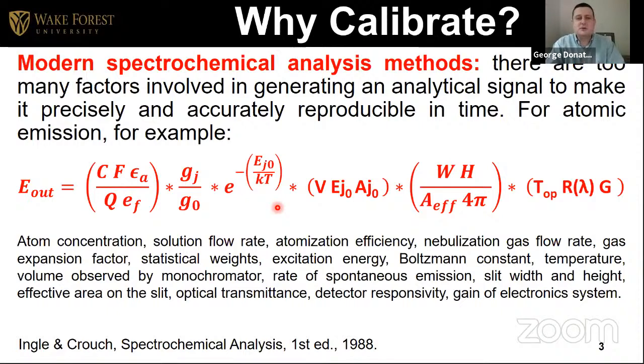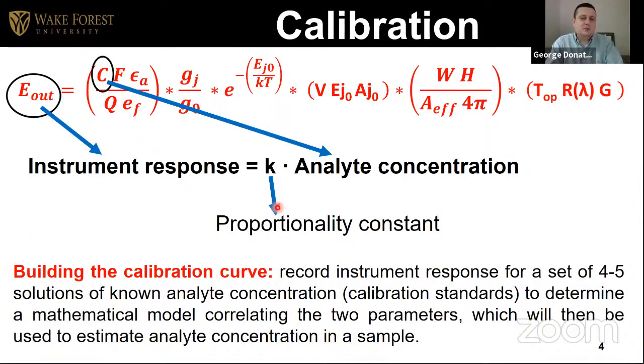In fact, it's advisable to rerun a calibration curve every 20, 25 samples, depending on how long each measurement takes. But from time to time it is good to do recalibration to make sure your signal matches the conditions of that moment in time. So usually what people do to overcome those variations due to the instrumentation, this is an example, an equation for atomic emission, but it could be any other kind of measurement using modern instrumentation. Usually what people do is to have instrument response and everything else becomes a proportionality constant and the concentration of the analyte. Then they run several solutions of known concentration, calibration standards, to determine a mathematical model that will tell you the relationship between instrument response and analytical concentration.